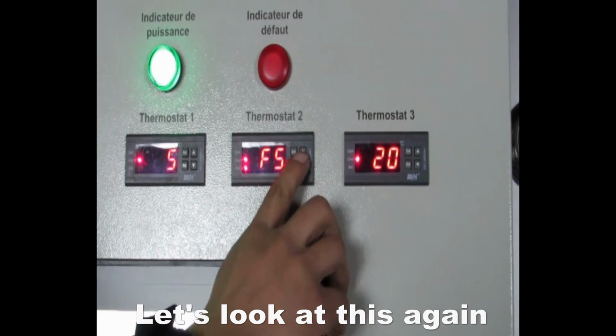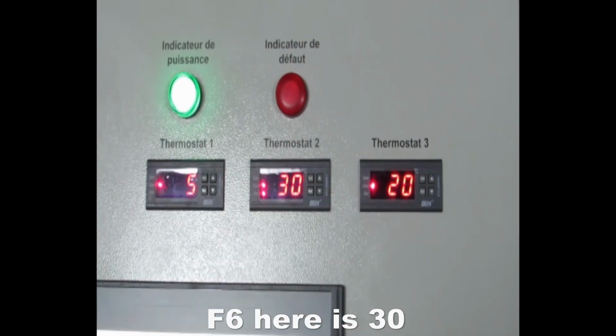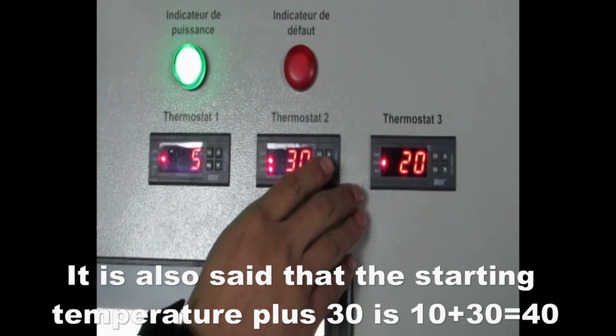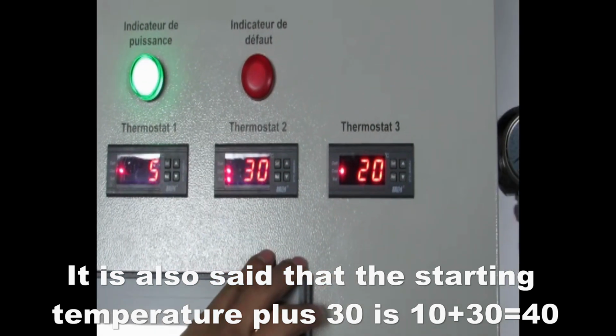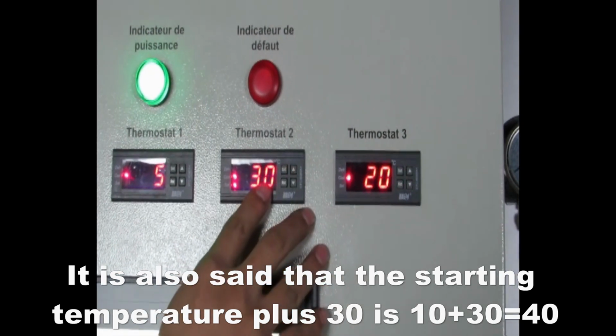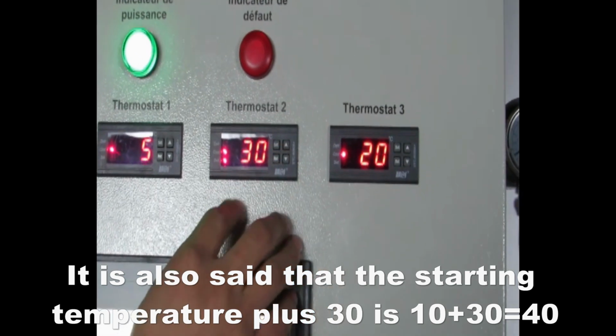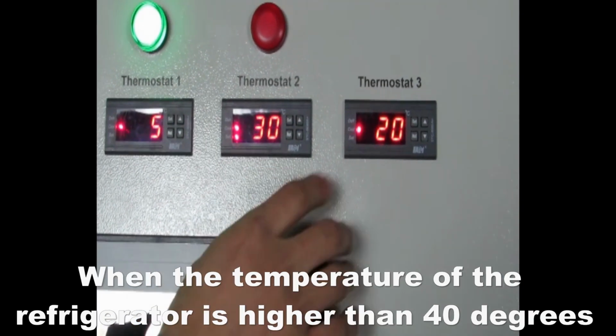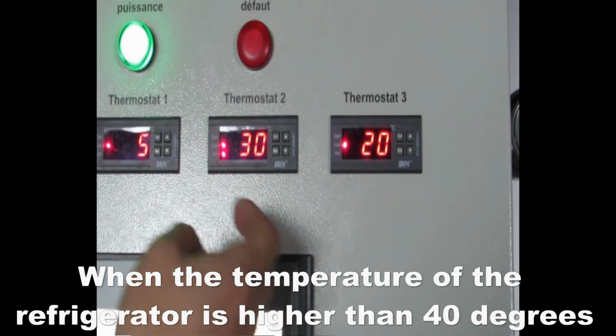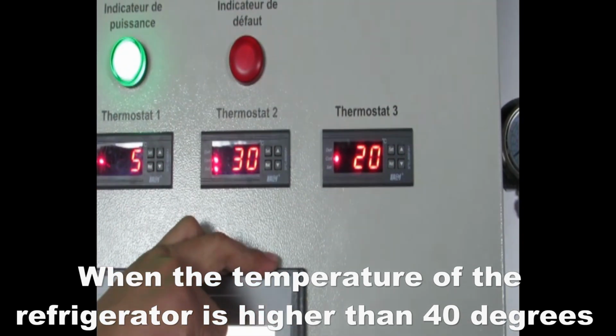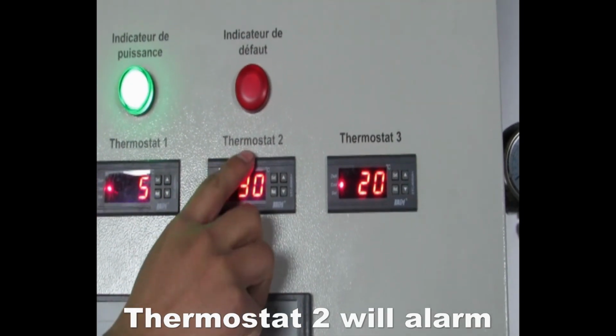Let's look at this again. F5 here is 30. That is, the starting temperature plus 30: 10 plus 30 equals 40. When the temperature of the refrigerator is higher than 40 degrees, thermostat 2 will alarm.